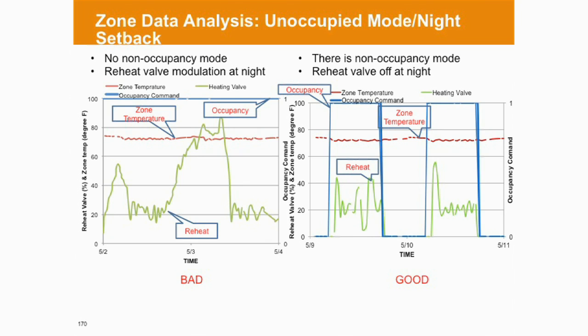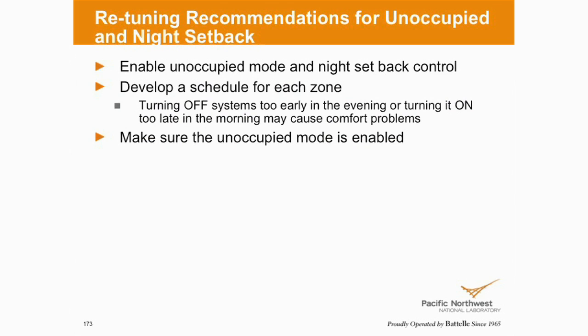On the right-hand side, the chart shows that we can just disable that reheat during unoccupied hours. The green line is the reheat valve command. You can see that on the left side, they don't have the occupancy mode. So what we want to do is enable unoccupied mode control. Ron has discussed this in the scheduling, and we want to turn off the system. So we want to develop a schedule for each zone, and make sure the unoccupied mode is enabled.